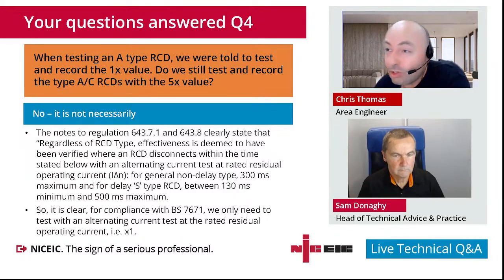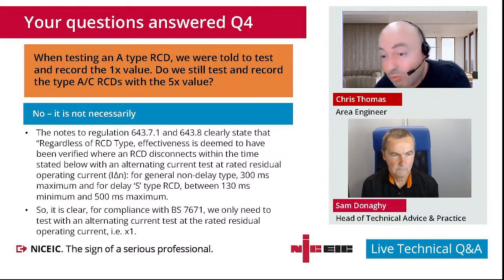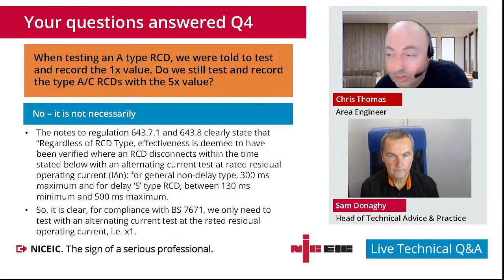One and also 643.8 also state several different values about different types of RCD, but ultimately they all state that you have to test them at their rated current, their rated trip current, and that would suffice from a wiring regulations point of view and an initial verification point of view, because Chapter 64 deals specifically with initial verification.